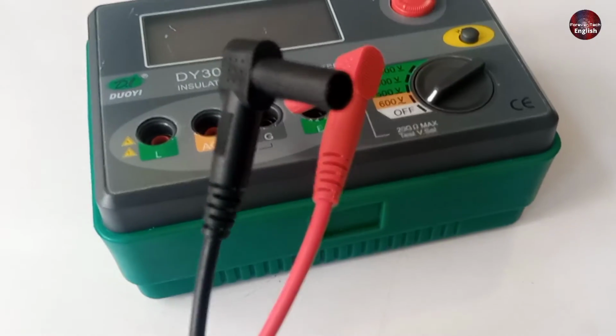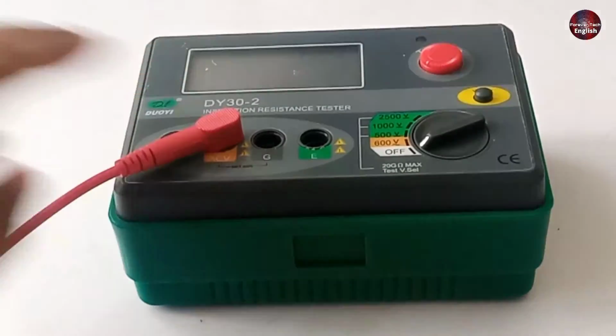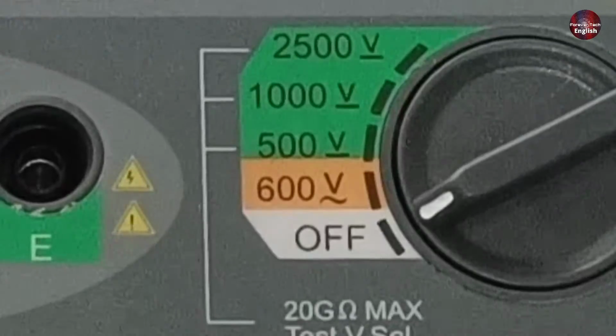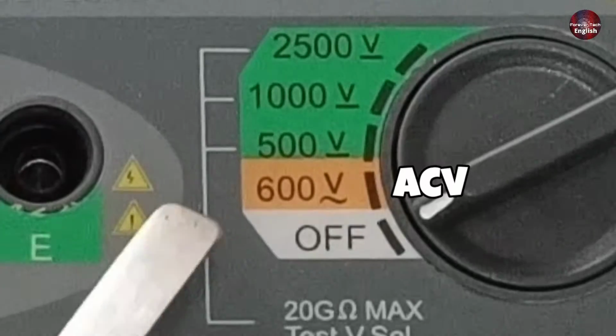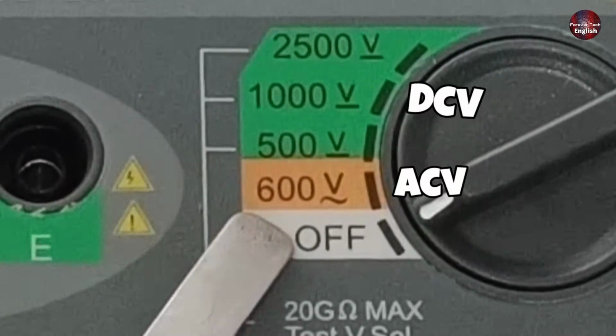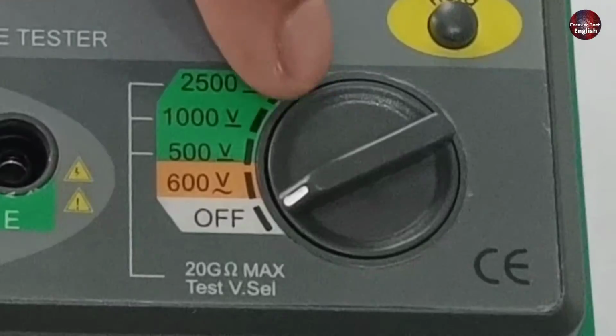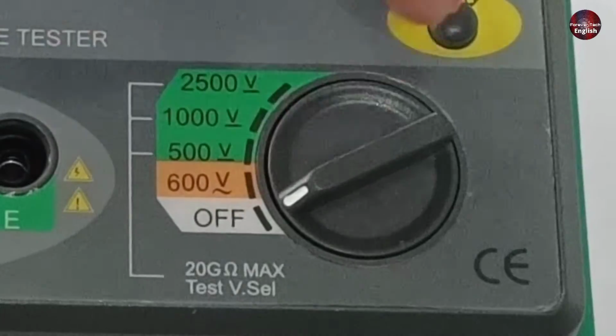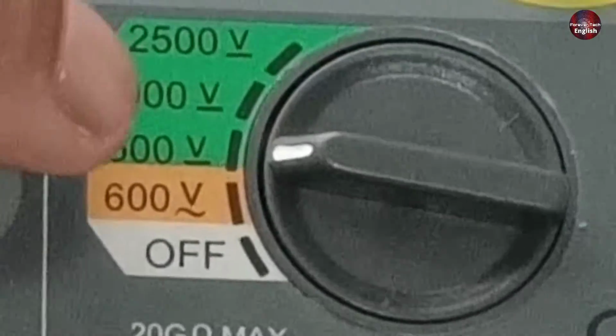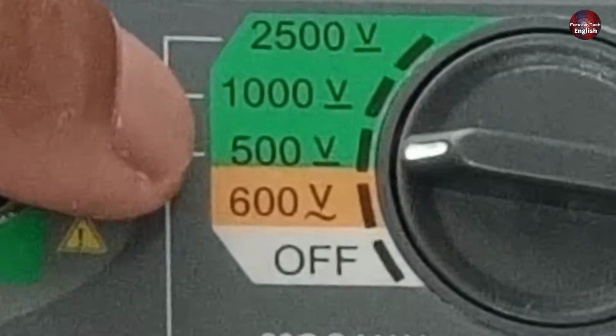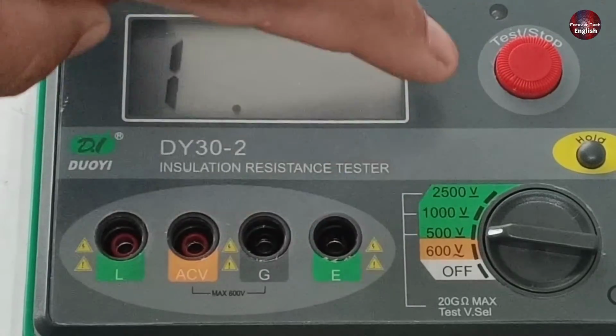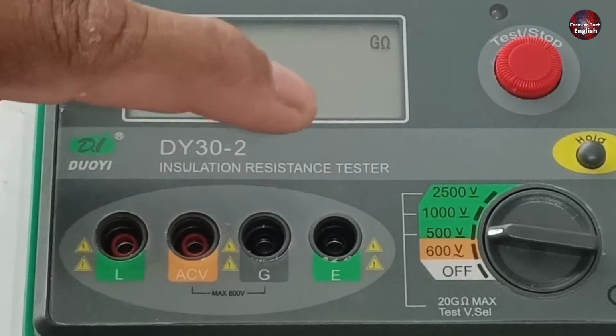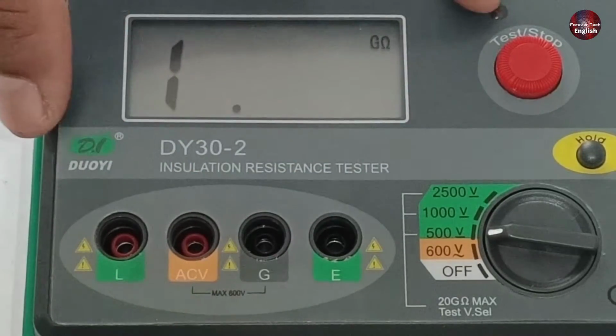And then, the probes will be attached to the ACV and ground port of the megger. I will tell you when to use a megger to test AC voltages and when to use the DC voltages to test devices. See, a rotary switch is installed with it. Now I will rotate it. I have set it to 500 DC volts according to my requirement. I will attach the probes to the device I want to check. I will tell you further in the video how to do it.